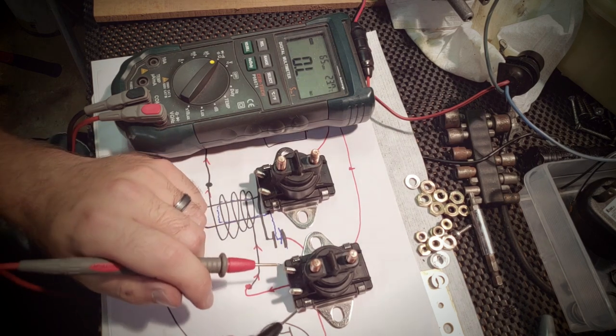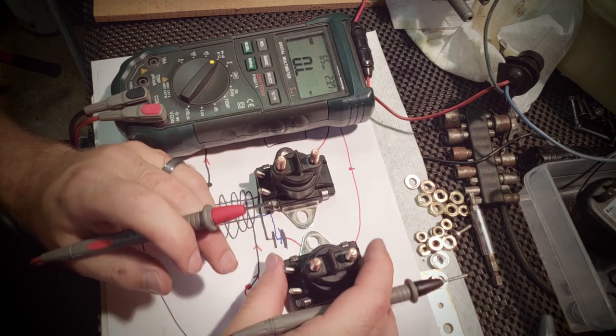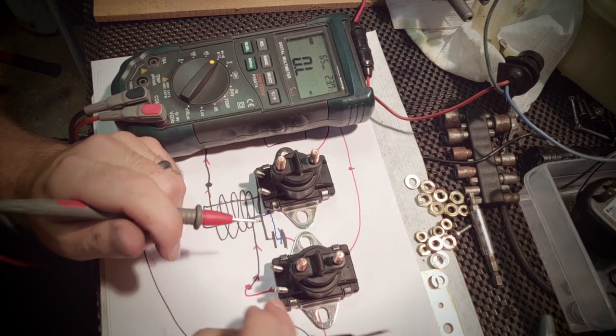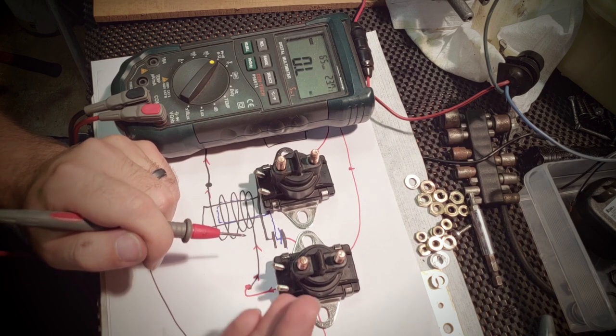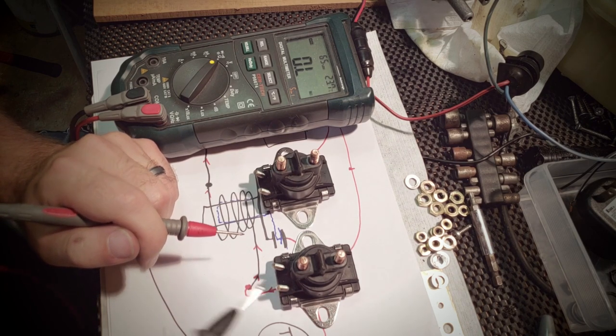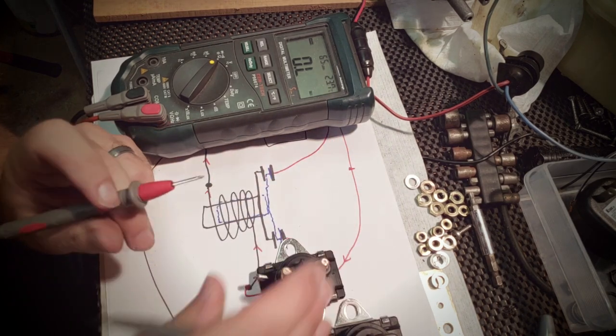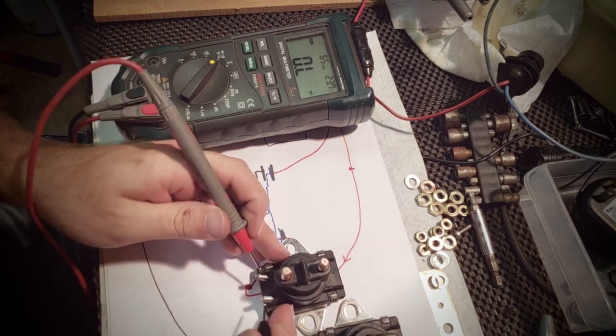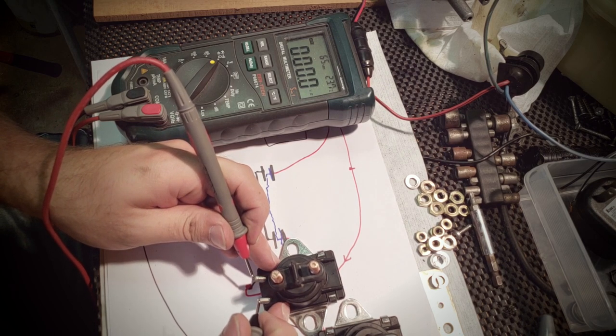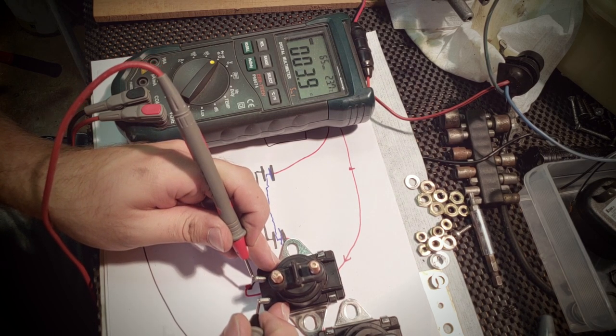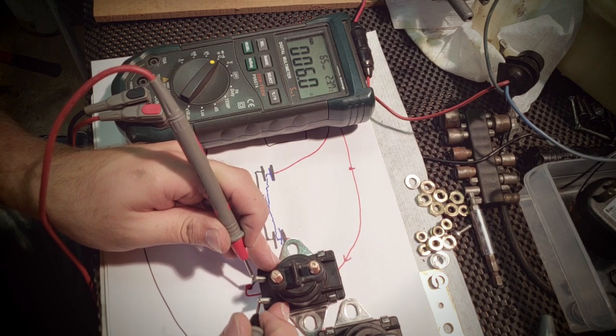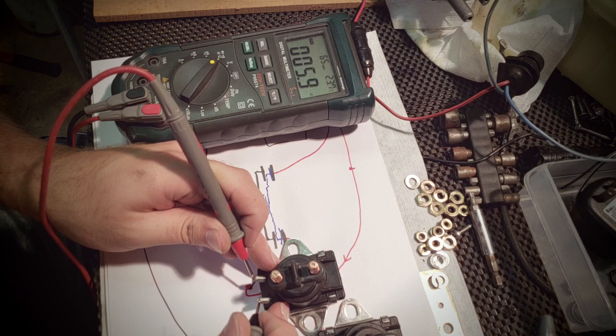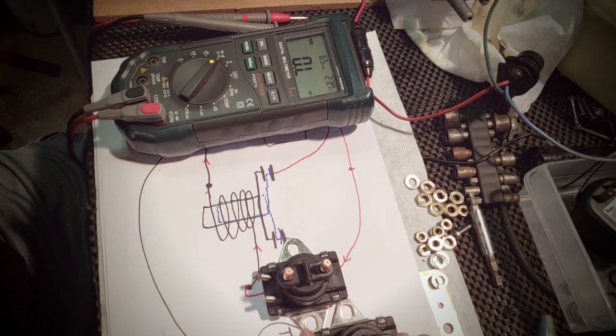Six ohms. That seems about right. The lower current or smaller these coils are, typically the higher the resistance is on this because you don't need as much current in that coil to create a high enough magnetic force. But because I know this thing takes a good bit of current, that's why I was able to guess that the resistance on this coil is going to be pretty low. And what we really want to see here also, since I don't know what the actual value is, is that they're going to be close to each other. And those are dead on. They're both 5.96 ohms, which is perfect.